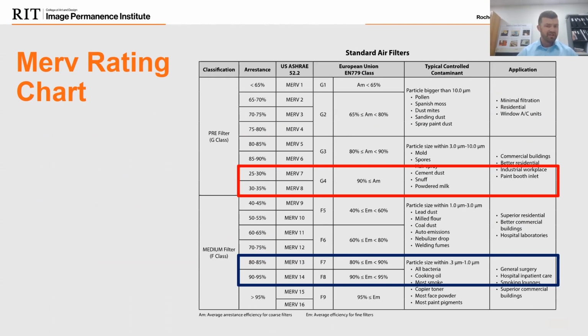It's even in many houses. And you could see what those filters block: mold spores, dust, cement dust, snuff, powdered milk. I don't know how much you see either of those in the air, but they're on that chart for potential contaminants that they'll block. You also, with COVID coming on, a number of institutions wanted to move up to MERV 13s, MERV 14s. An example of those is down here. They'll block more materials. It'll also block cooking oil, most smoke, copy toner. And as we're down in, say, MERV 14, we also block all the previous things: lead dust, flour, coal dust, things like that. So anything in this, if you're at a MERV 14, everything previously up here, you'll block as well.